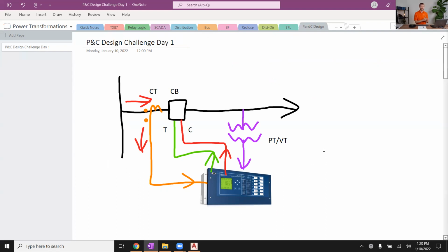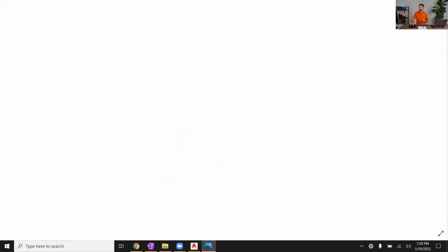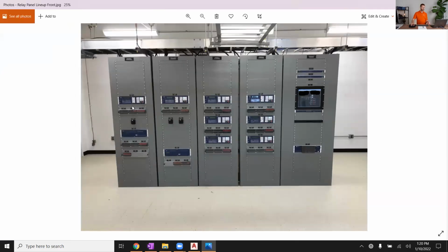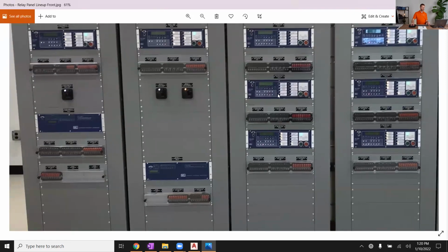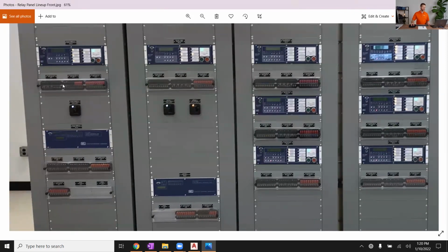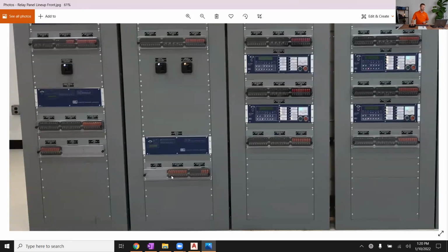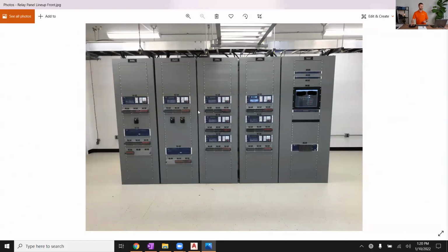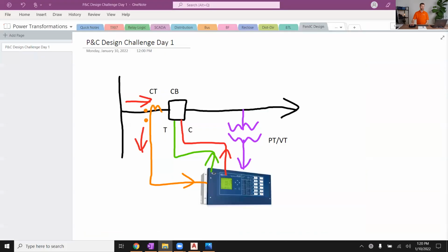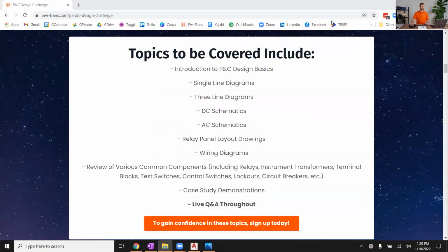But test switches are very often used with our protective relays. In fact, in some of those pictures I showed you earlier of the relay panel lineups, you see under each relay there's a set of test switches, or one or more test switches in some cases. Sometimes you have 3 sets, 10, 10, and 10, so that's 30 test switches. Sometimes you can order it with 20 or with just 10, whatever your needs are for that relay's application. But what is a test switch? I think I can squeeze this into our last 10 minutes together.